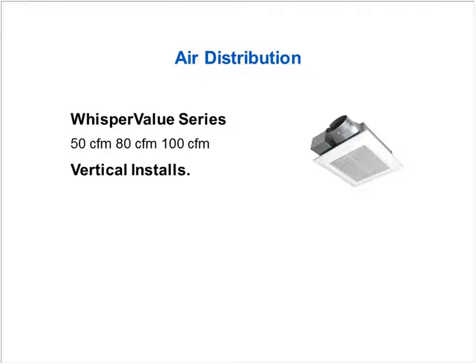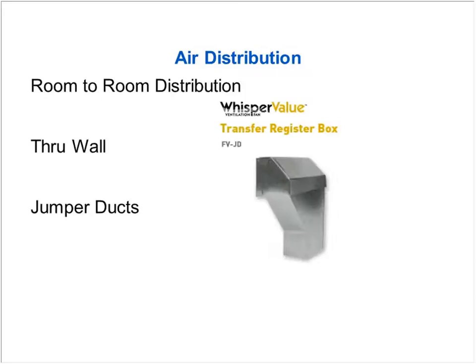Now the Whisper Value, we see this in vertical installs. So what we'll do is we'll put this on the wall, on an interior wall, as high as we can get it. And then I literally have a transfer box. We'll drive that air down through the chase. It's basically in a duct inside the chase, the wall cavity chase, and then exhaust that out to the bottom. And I can bring that out to the other side. So if I have a fan on this side of the wall, I can drive that air down, and I can exhaust it out on this opposite side, or I can exhaust it back into the room and create that thermal loop.